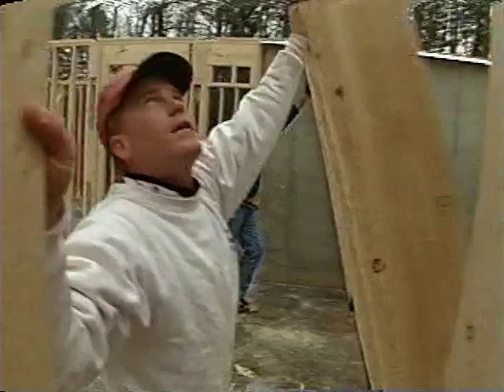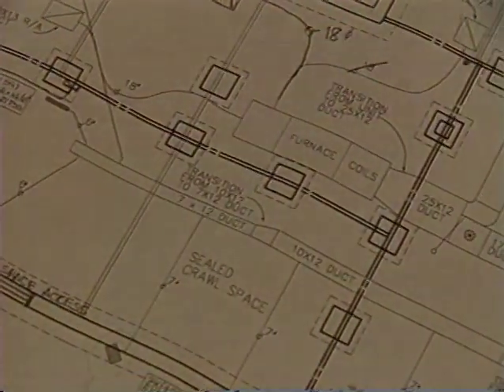Jeff bases his duct design on information from a computer model based on the load calculation standards found in the Air Conditioning Contractors of America, or ACCA, Manual J. He factors in the amount of glass in the house, the framing materials used, insulation, flooring, orientation to the sun, and much more. The goal is a room-by-room computer model giving heating loads, cooling loads, and airflow calculations for each room. What follows is a duct design — a useful management tool for people in the field, to coordinate with the framer and plumber and to generate material lists to get the job done effectively.